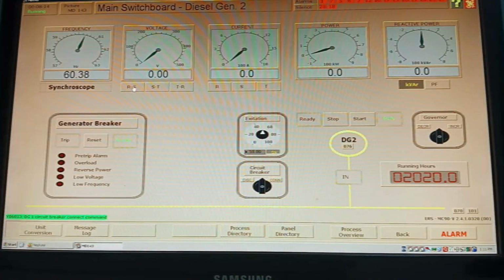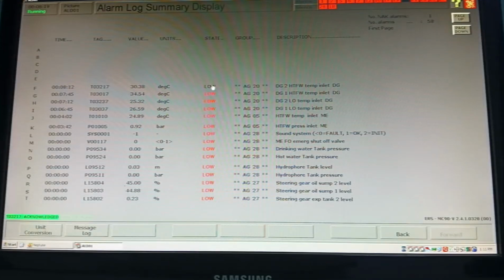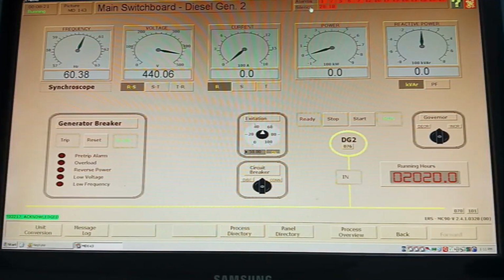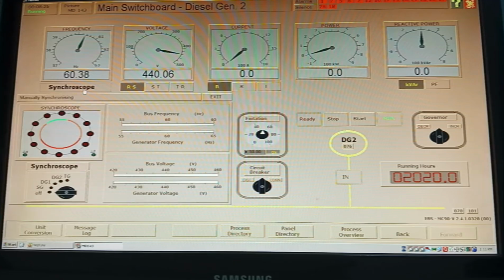So the same thing to DG2, but you have to synchronize the incoming generator now. So to synchronize the generator, you need to turn on your synchroscope. Your DG2 is the incoming generator, so put it on DG2 and then you should move this light so that it takes a full revolution, and once it reaches 11 o'clock you should connect the breaker. So to start moving it, you have to increase your governor and take it off.